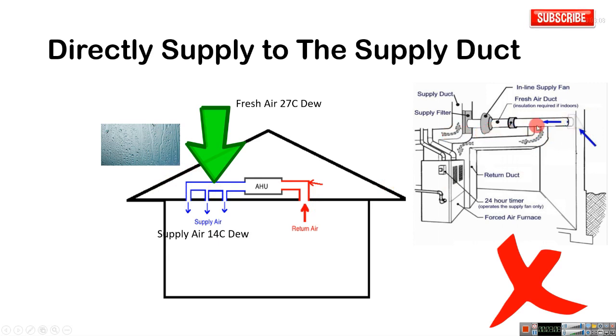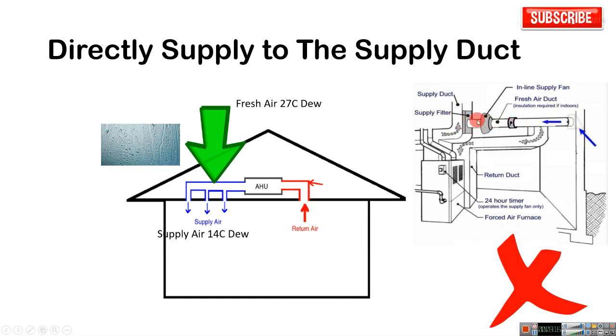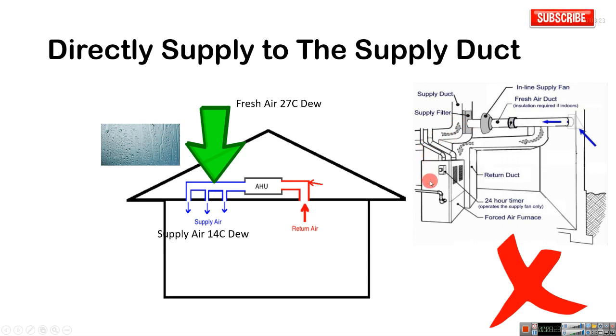Look at this picture — you can see this room's wrong practice. This is the supply line. Fresh air is connected to supply here, and there will definitely be condensation. The condensate goes backward through the duct edge.